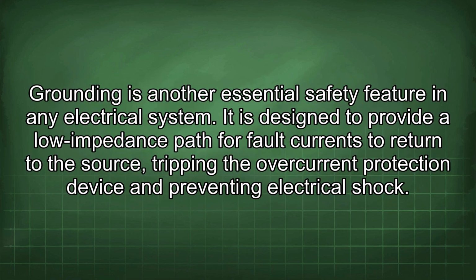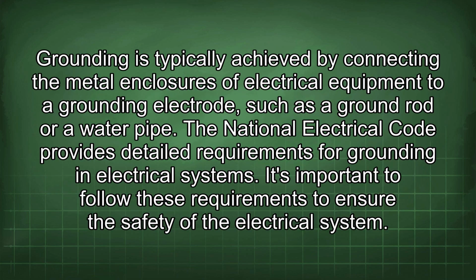Grounding is another essential safety feature in any electrical system. It is designed to provide a low impedance path for fault currents to return to the source, tripping the overcurrent protection device and preventing electrical shock. Grounding is typically achieved by connecting the metal enclosures of electrical equipment to a grounding electrode, such as a ground rod or a water pipe. The National Electrical Code provides detailed requirements for grounding in electrical systems. It's important to follow these requirements to ensure the safety of the electrical system.